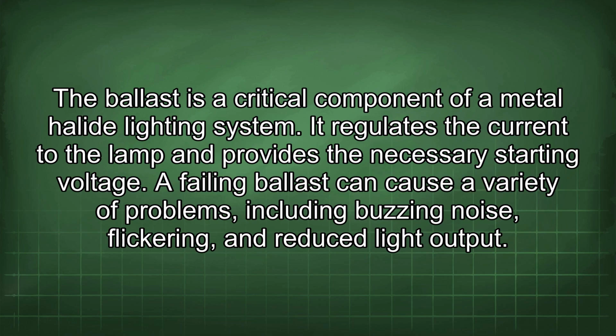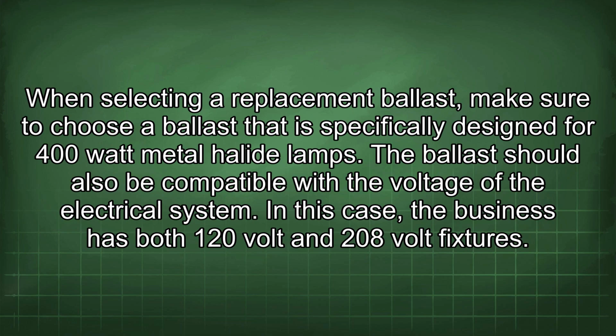The ballast is a critical component of a metal halide lighting system. It regulates the current to the lamp and provides the necessary starting voltage. A failing ballast can cause a variety of problems, including buzzing noise, flickering, and reduced light output. When selecting a replacement ballast, make sure to choose a ballast that is specifically designed for 400-watt metal halide lamps. The ballast should also be compatible with the voltage of the electrical system.